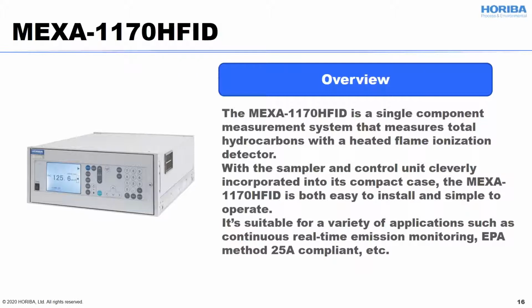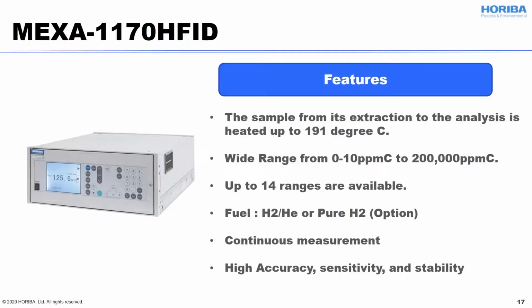It is suitable for a variety of applications such as continuous real emission monitoring or EPA Method 25A compliance, etc. MEXA-1170HFID uses a hydrogen flame ionization detector in a heated block to prevent the loss of high molecular weight hydrocarbons and to provide long-term stability and reliable performance in the analysis of low trace concentration levels of hydrocarbon contaminants. The sample from its extraction to the analyzer is heated up to 191 degrees C.